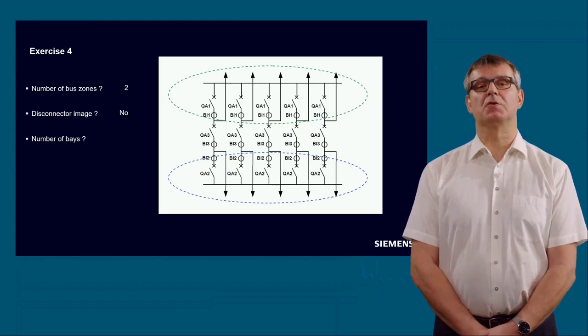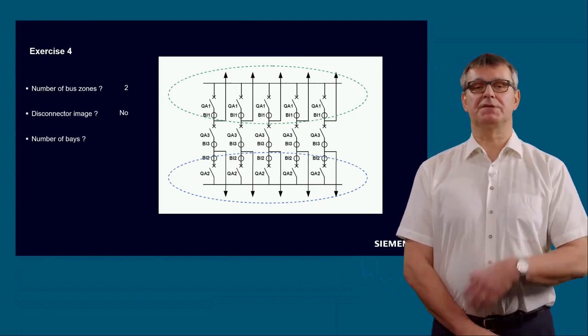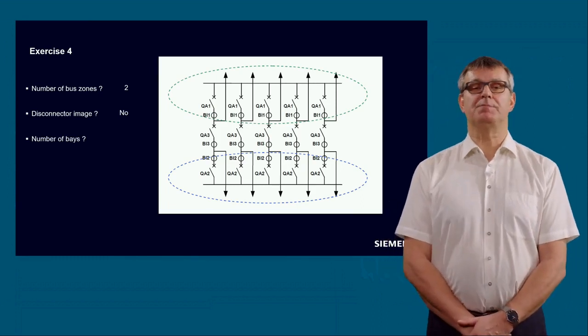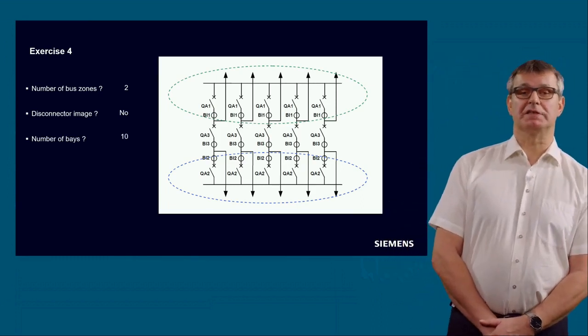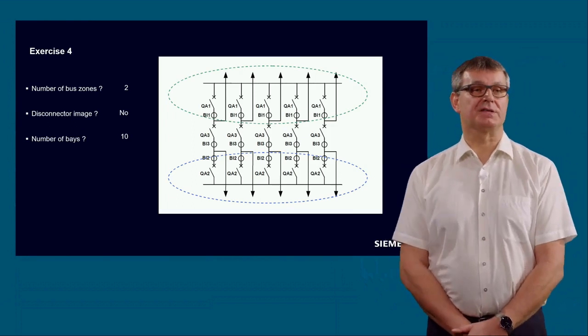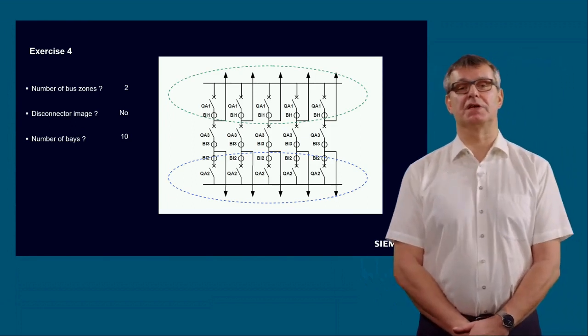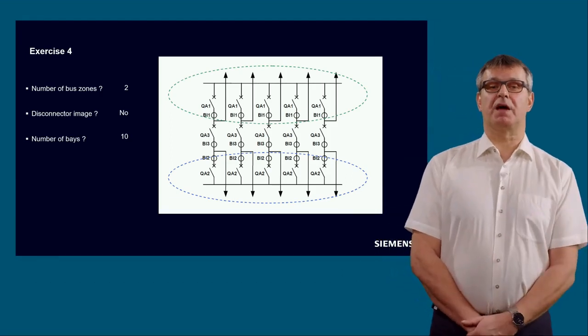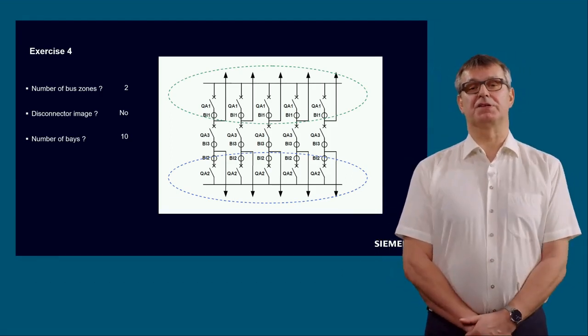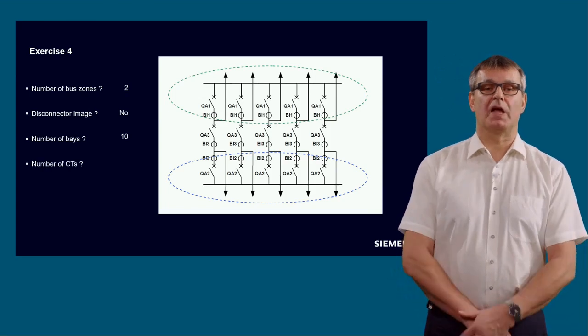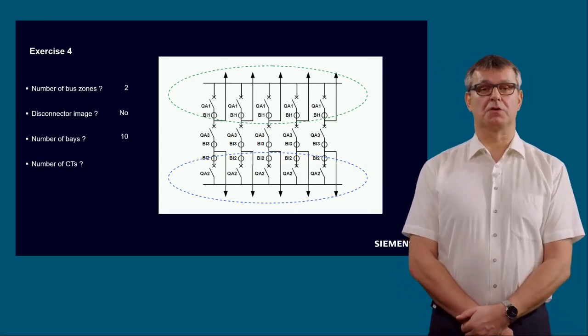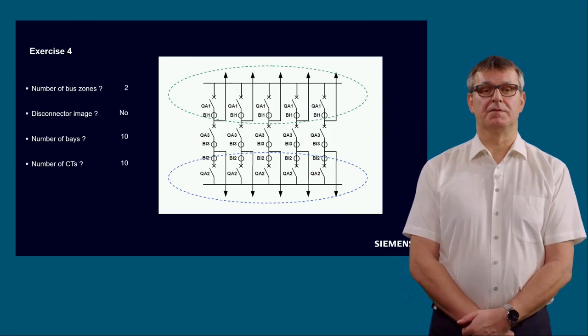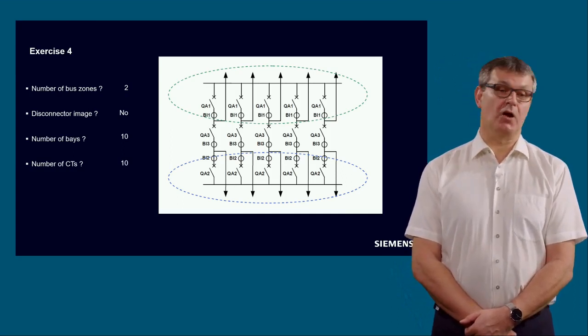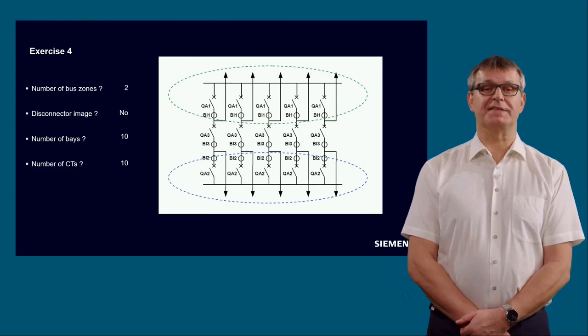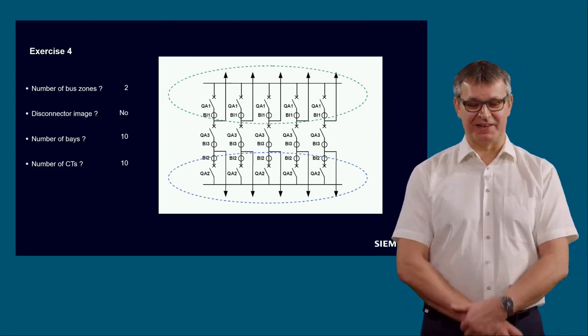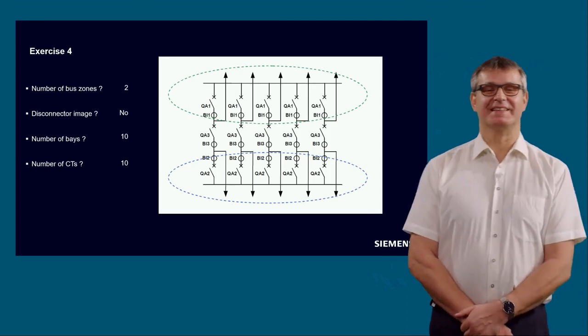Number of bays. We have 5 diameters, but it will be split into 2 independent bus zones. So we need in total 10 bays: 5 bays directly assigned to the upper busbar and 5 bays assigned to the lower busbar. And the number of CTs here, also quite easy, is also 10. So I hope you were all quite successful answering my short exercises.